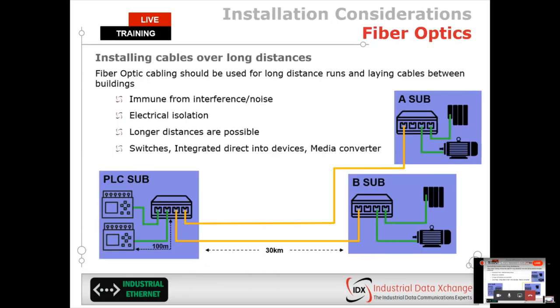So as an example of integrating fiber optics, on this section over here I have my substation for my PLC. I've got my two PLC controllers linking into a switch, and then I've got my A sub and my B sub - these are two remote substations. Within my individual subs I have a maximum of 100 meters, so I can have 100 meters of copper cable connecting my switch to my devices. But the distance from my PLC sub to each of these substations is about 30 kilometers - a pretty long distance, massive site this. So pretty much one of the only options I have is to run fiber optics.